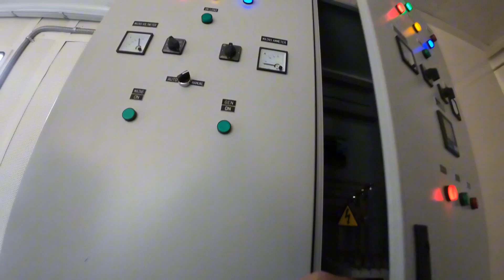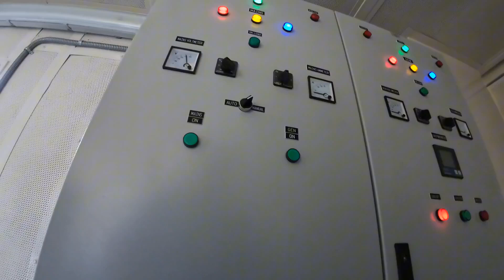So now we have also the mains power, so we can try manually closing the breaker. We will manually close it from the genset side. It is working. As you can see, it is transferring to the genset side, and we are going to put in the mains. So it is working on the mains.